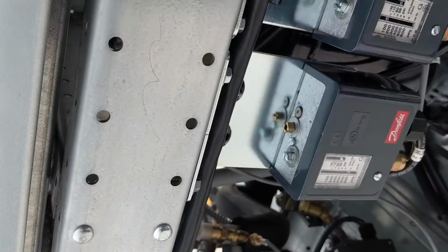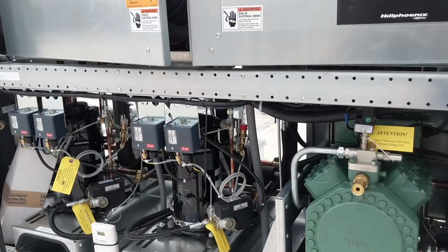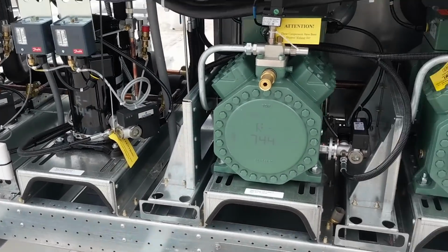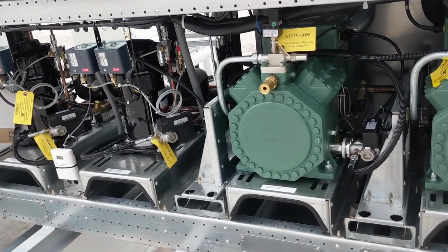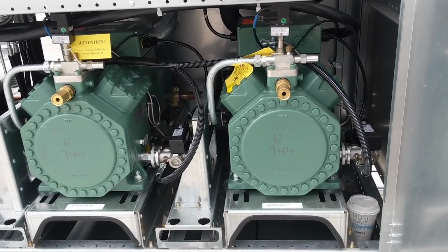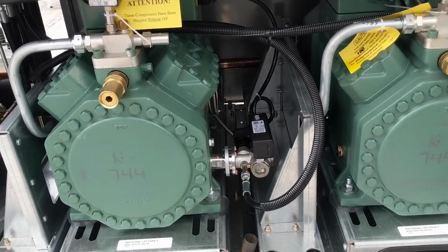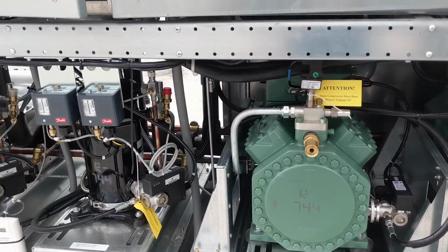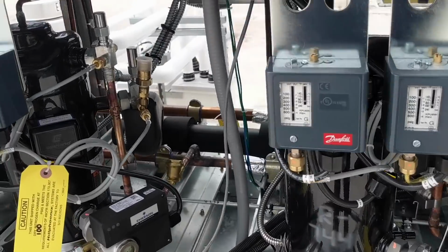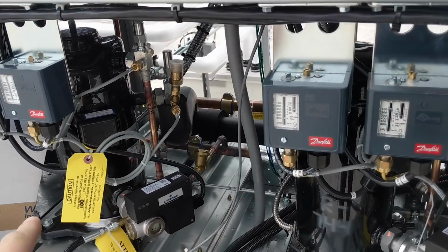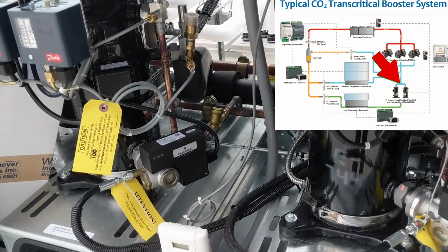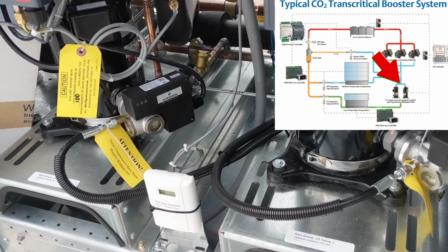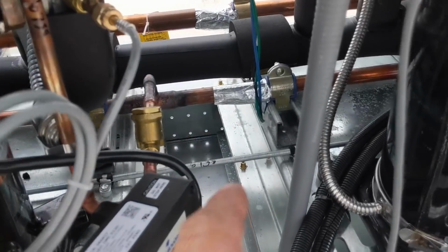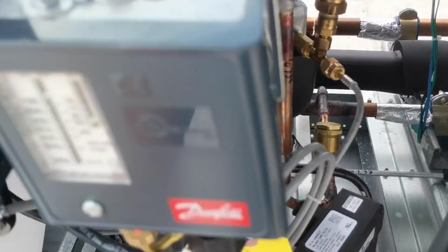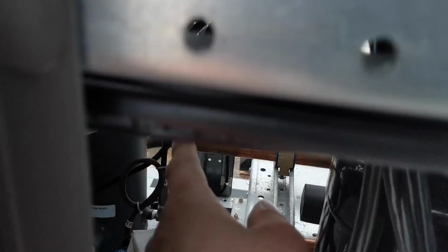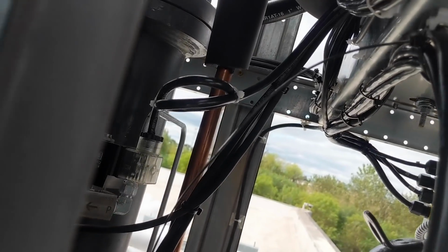This is the transcritical CO2 rack we just started up. You got 2 low temp compressors, 410A scrolls, and you got 2 medium temp compressors. So this rack is transcritical, so it's actually compressing CO2. We got the CO2 scrolls over here. You have 1 digital compressor, 1 normal compressor. They're using Emerson OMC oil controls. Discharge header back here for the low temp flows up and into the medium temp suction header.